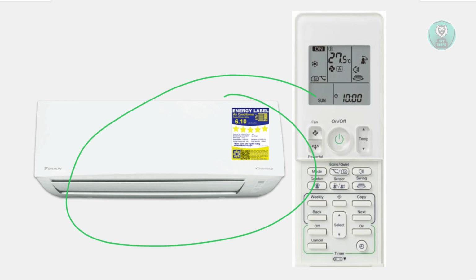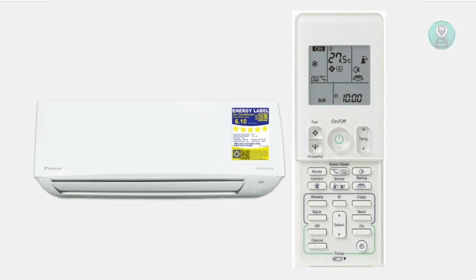Now if the error persists, there are still a few things that you can try doing here. Next, you may want to inspect the communication wire. A loose or damaged communication cable can cause the U4 error. How do you check it? In this case, you want to locate the communication wire connecting the indoor and outdoor unit. Look for any signs of damage, loose connections, or disconnections. Secure all connectors properly, and if the wire is damaged, you may need to replace it.